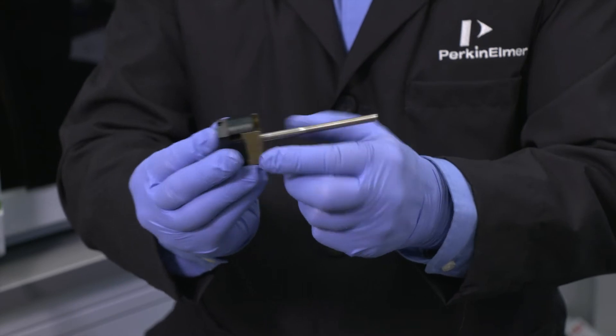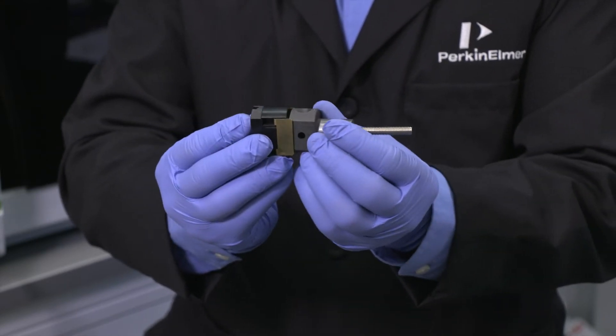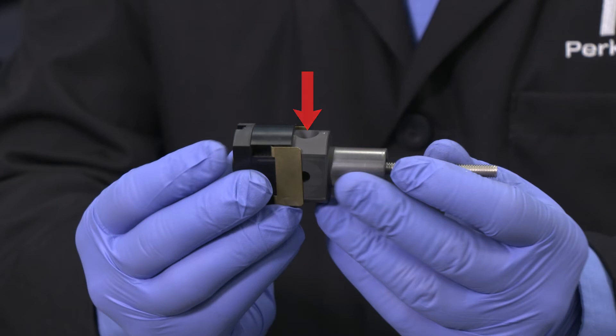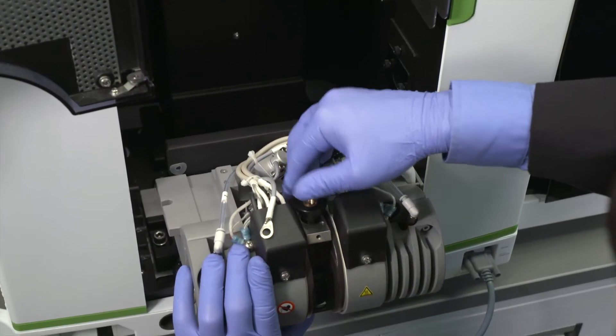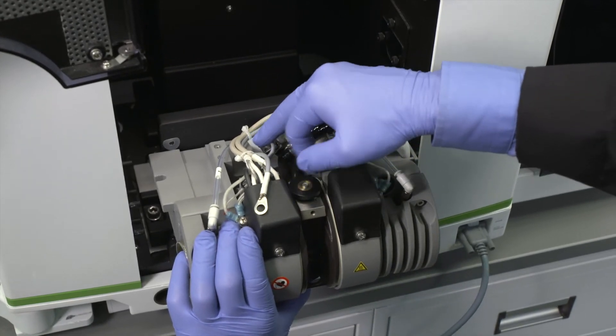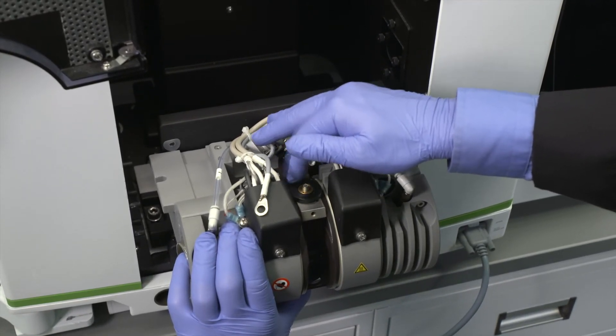Put the threaded cylinder into the opposite end of the housing. Orient the graphite contact with the dosing hole to the top. Then screw the bolt into the cylinder until the contact is pressed up against the housing. Again, ensure the dosing hole is at the top.